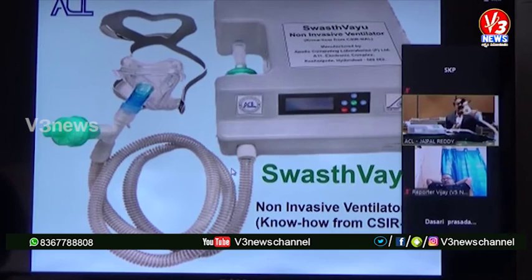Because this is open. This machine is actually a non-vented mask, because leakage should not happen. The corona droplets should not leak out from here. The moment I put this on, you see the alarm has gone. So alarms are there for various conditions. This is the open condition, and also when the power is dropping below 33%, an alarm comes. This is like a notebook computer, where when the power is coming down, we get an alarm.